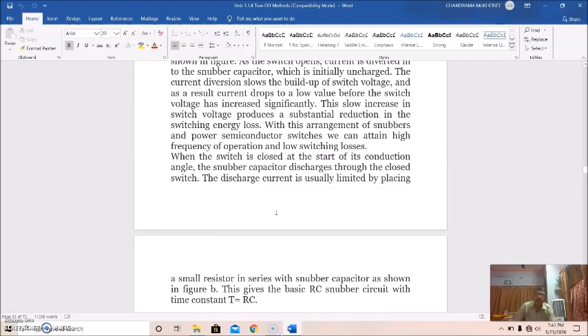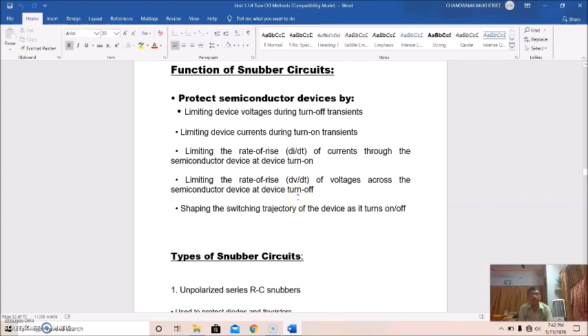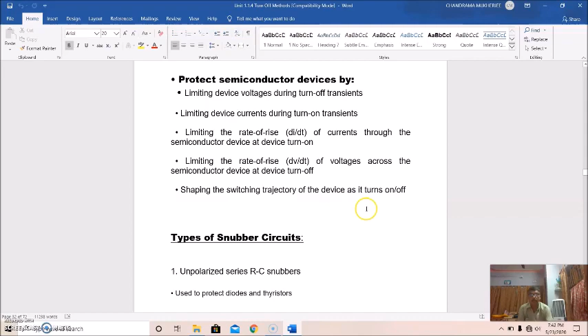So from this arrangement, we can say the function of the snubber circuit is to protect semiconductor devices by limiting device voltage during turn-off transients, limiting device current during turn-on transients, limiting rate of rise of current, di/dt, at device turn-on, limiting rate of rise of voltage, that is dv/dt, across the semiconductor devices at device turn-off, and setting the switching trajectory of the device as it turns on or off.